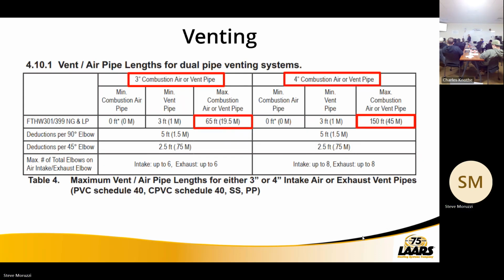Venting, again, we have 3 or 4 inch vent here. If you're using 3-inch vent, you're good for 65 feet each. But let's just example talk about the exhaust. Don't forget for every 90 on this left-hand column, 5 foot for every 90 would be calculated in, 2.5 feet for every 45. If I was 50 feet and had 4 elbows, right, I'm now over my 65 foot allowance. I have to go to 4-inch, which now I can go up to 150 feet. And it's still going to use the same calculations for the 90s and 45s.